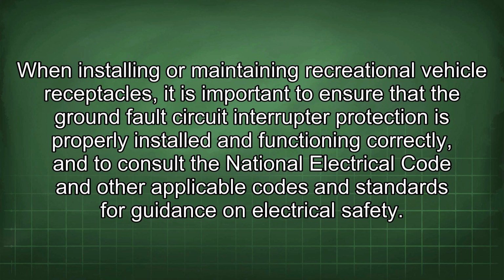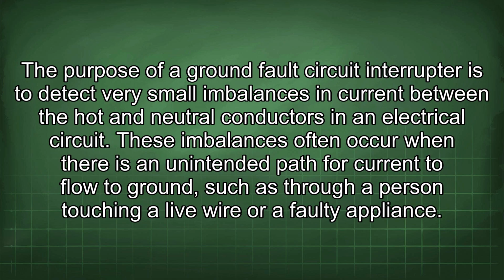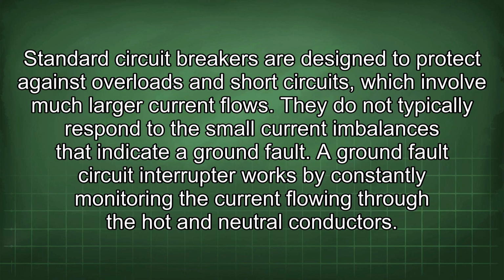on electrical safety. The purpose of a ground fault circuit interrupter is to detect very small imbalances in current between the hot and neutral conductors in an electrical circuit. These imbalances often occur when there is an unintended path for current to flow to ground, such as through a person touching a live wire or a faulty appliance. Standard circuit breakers are designed to protect against overloads and short circuits, which involve much larger current flows. They do not typically respond to the small current imbalances that indicate a ground fault.